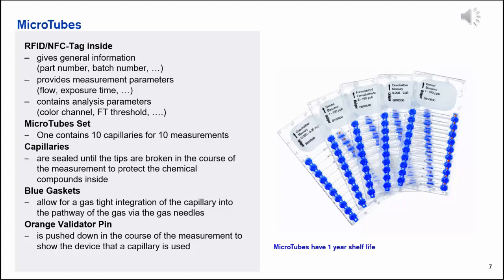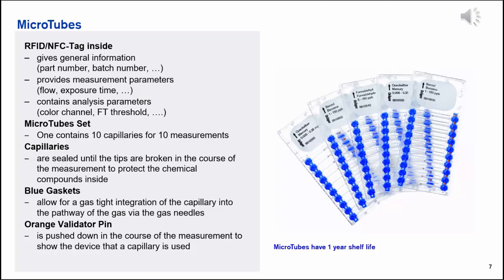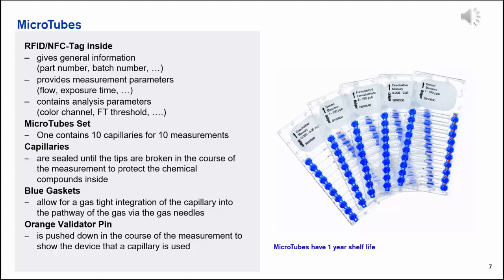The blue sealing septums you see here at both ends provide very gas-tight seal to the pump system during the measurement. The relevant information, as I say, regarding the calibration for each analyte to some degree is printed on the RFID tag. You'll find the name, the measurement range, and also the part number. But then additional information with regards to the flow rate, the exposure time, the color channels and the evaluation of the front tracking algorithm, as we call it, which I'll explain in a little more detail here in just a bit, for each particular microtube is encoded in the RFID tag. So basically that means that all relevant information about carrying out a measurement is stored here and is valid over the shelf life of the microtubes. And I also do want to mention at this juncture that each microtube actually has a one-year shelf life from the time it leaves our facility in Memphis.